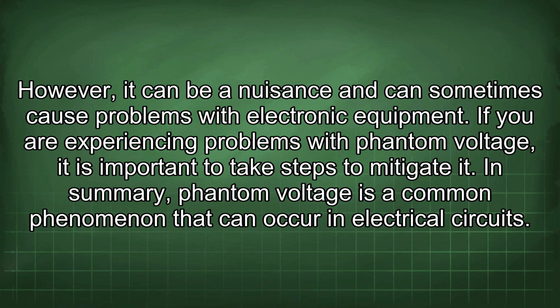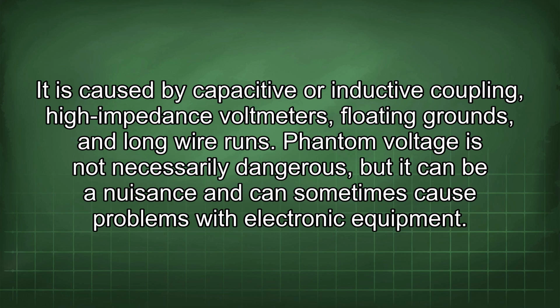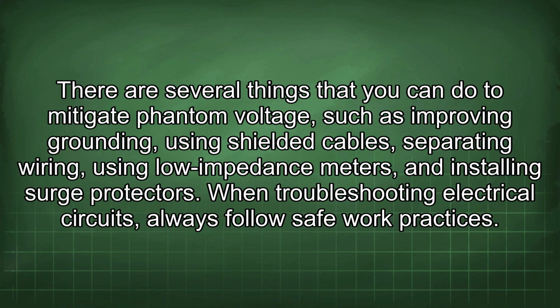In summary, phantom voltage is a common phenomenon that can occur in electrical circuits. It is caused by capacitive or inductive coupling, high impedance voltmeters, floating grounds, and long wire runs. Phantom voltage is not necessarily dangerous, but it can be a nuisance and can sometimes cause problems with electronic equipment. There are several things that you can do to mitigate phantom voltage, such as improving grounding, using shielded cables, separating wiring, using low impedance meters, and installing surge protectors. When troubleshooting electrical circuits, always follow safe work practices.